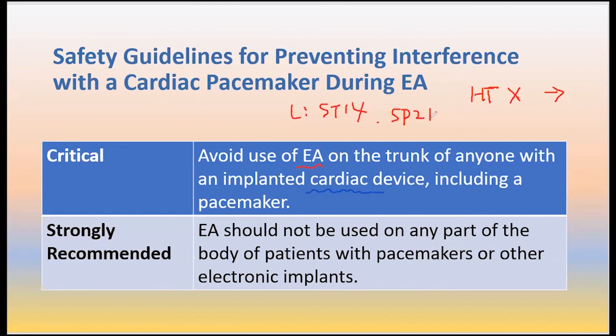But occasionally, because of natural development, something goes wrong and all the organs are in the opposite direction. In that kind of case, their heart may be on the right side. Also some people have lung issues that may push the heart to the right side. So that's another issue. Make sure the patient's heart is not on the right side. Generally speaking, the left side is the dangerous situation. For any points, the electrical connection should not pass through the heart.